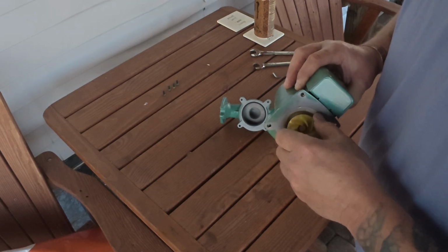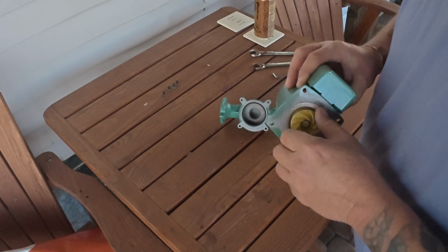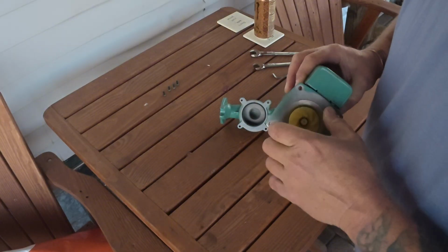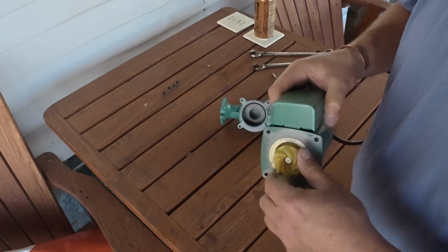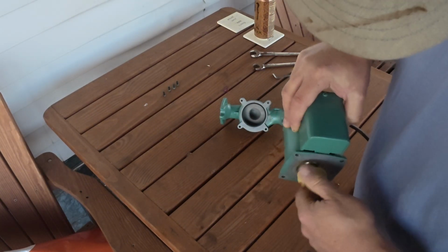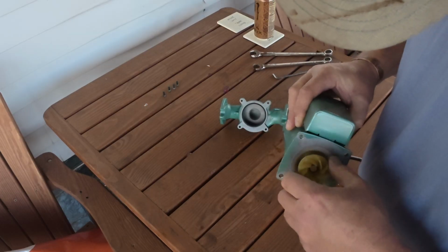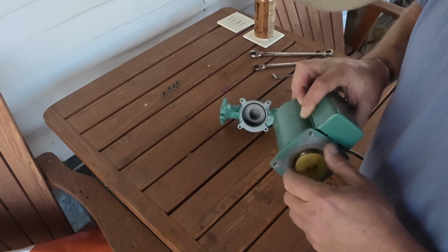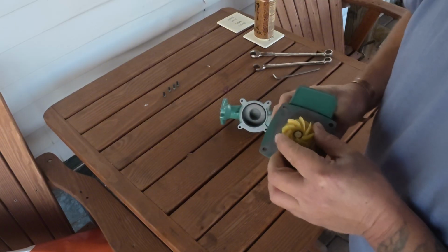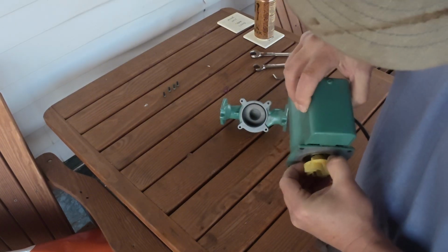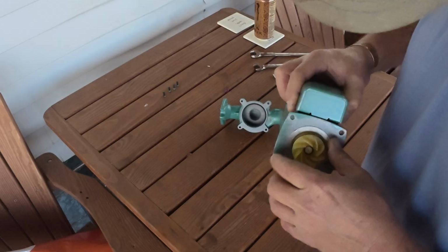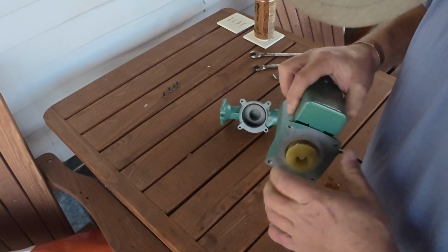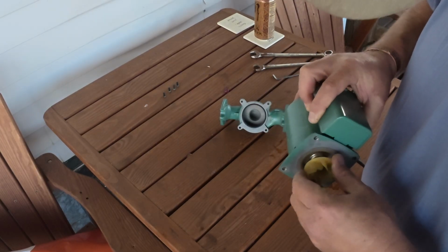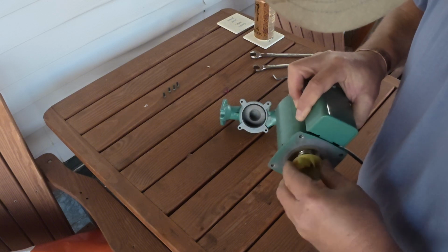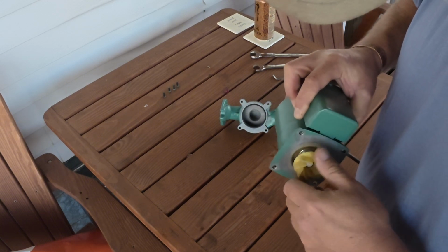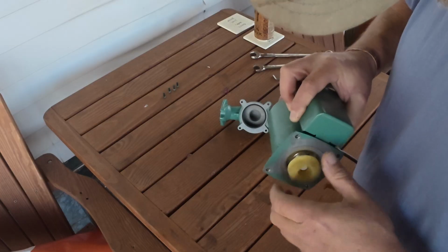Oh, there we go - that made a difference. What was that? Did you guys hear the noise difference? Something's going on inside that motor. That's exactly where my noise is coming from. I don't know if that's a bearing issue inside of the motor.